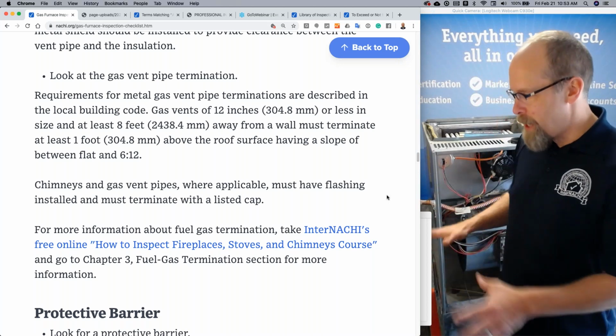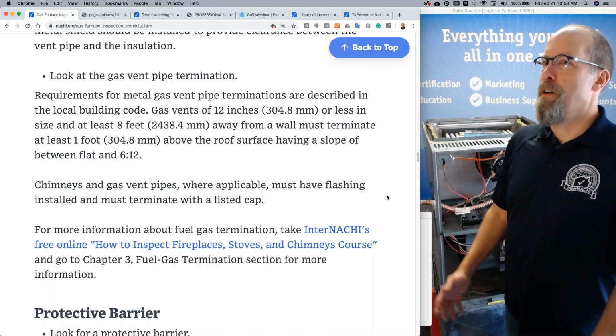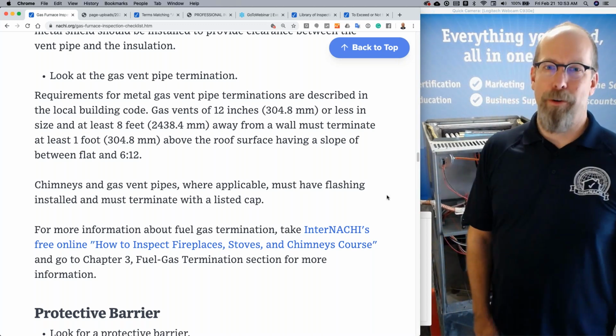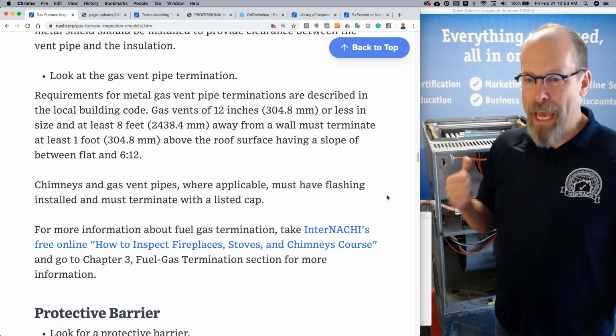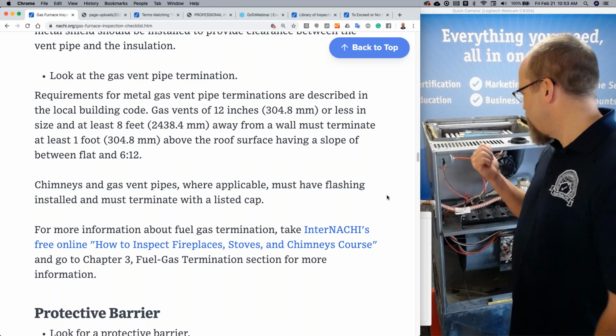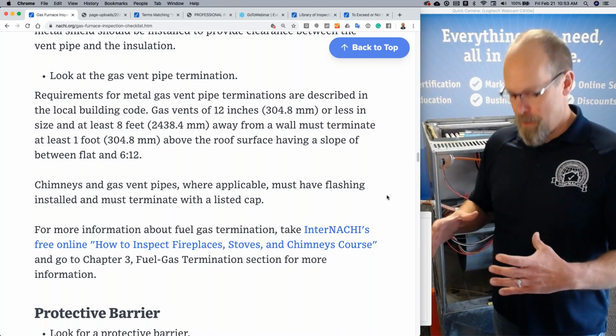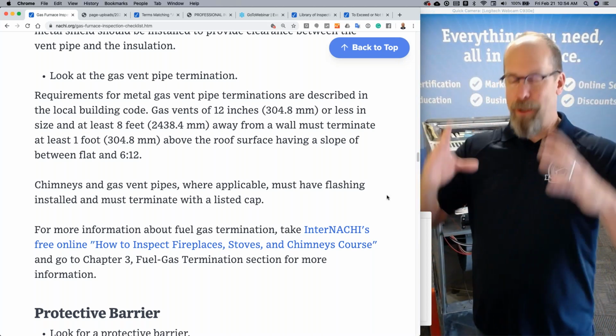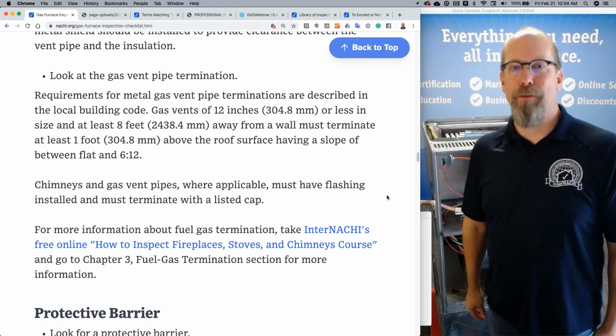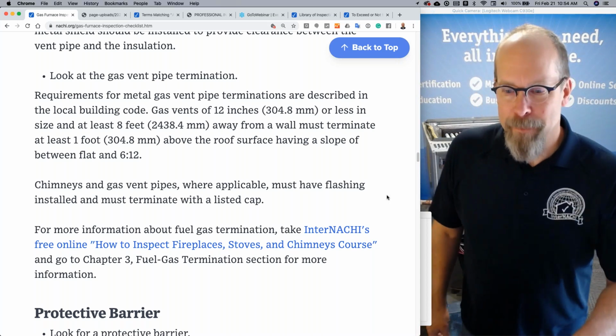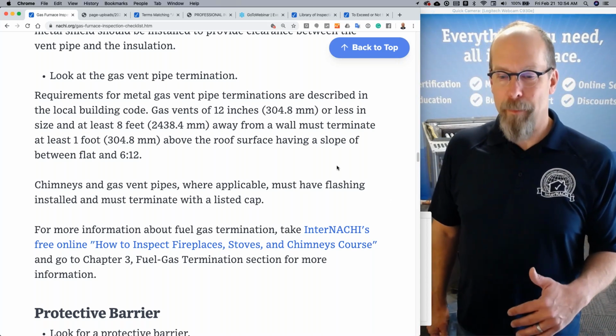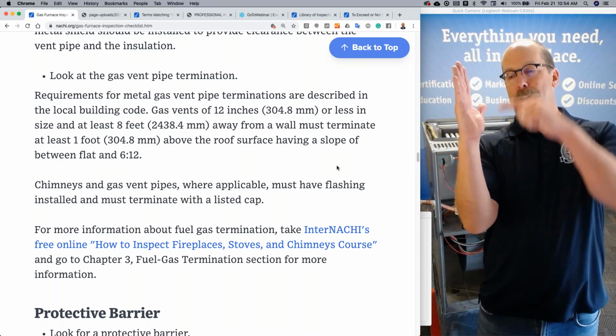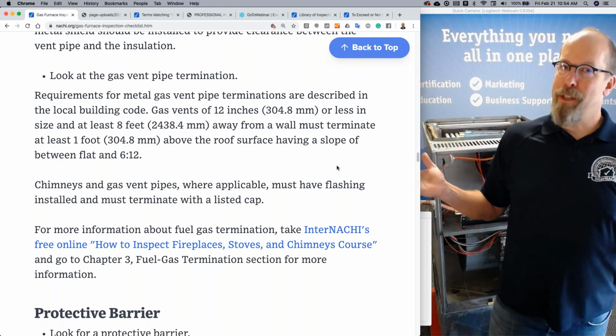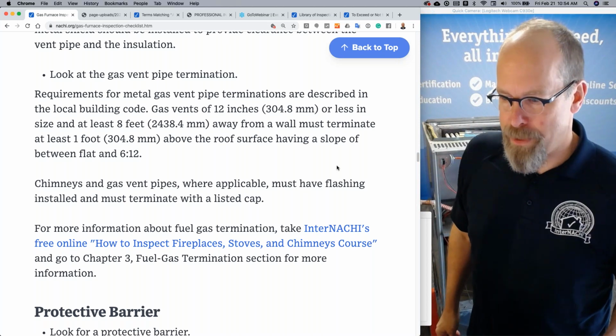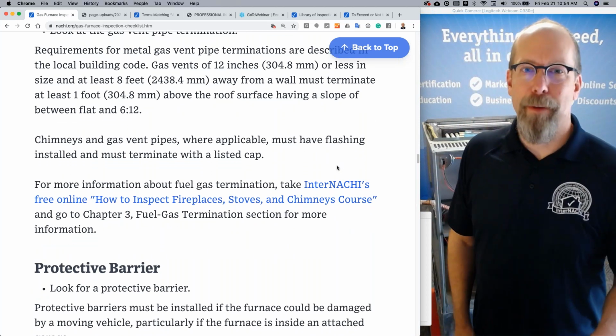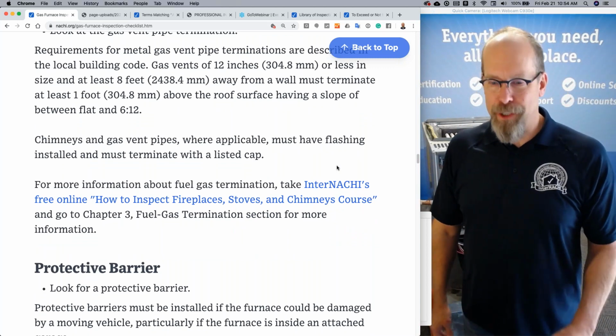And it's unlike a masonry chimney stack of a fireplace. That's the 3-2-10 rule. This is different. The metal gas vent terminations for gas-fired systems like this are shorter, right? And it's a big diameter pipe too, 12 inches or less, you need about a foot off the roof surface. They're going to be a little bit higher usually, I've found. And that's for a roof surface having a slope between flat and 6/12. So the steeper it is, the higher the pipe needs to be, right? But between flat and 6/12, which is a very common slope for roofs in the United States, you're going to find a short little gas vent termination. Chimneys and gas vent pipes, where applicable, must have flashing installed and must terminate with a listed cap.